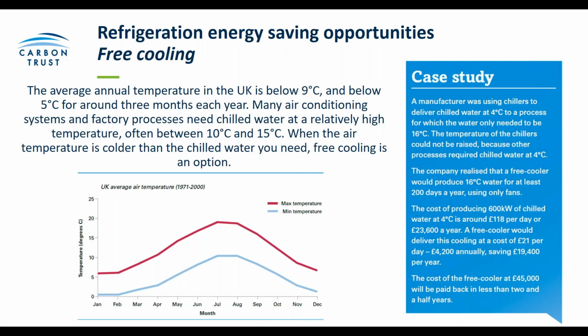The next part of the energy saving opportunities section is free cooling. If the external ambient temperature is cold enough, which in the UK it tends to be, then you might not need to work compressors at all. The case study on the right shows a manufacturer we spoke to through the Green Business Fund who had a requirement for chilled water. They installed a free cooler that would produce 16-degree water for 200 days a year, only using fans and not the compressor at all, making use of the cool external ambient temperature. This saved around £19,500 a year, and although the project cost £45,000, it paid back in simple terms in 2.5 years. Again, a really attractive investment if you've got the capacity and the requirement to use it.